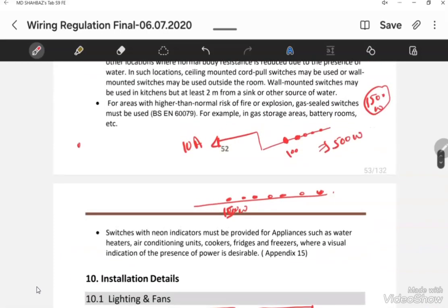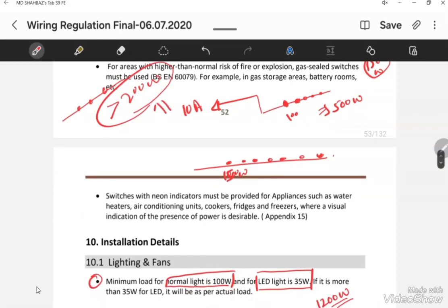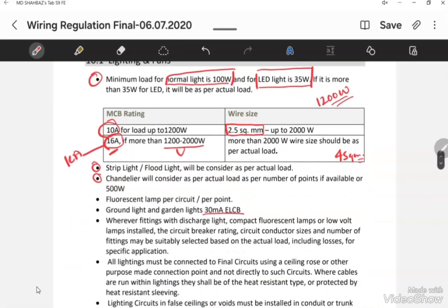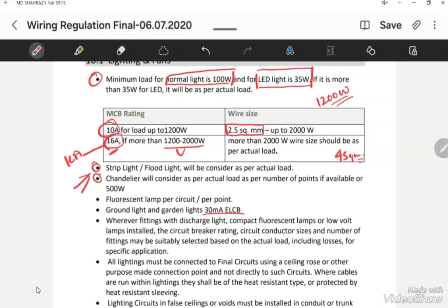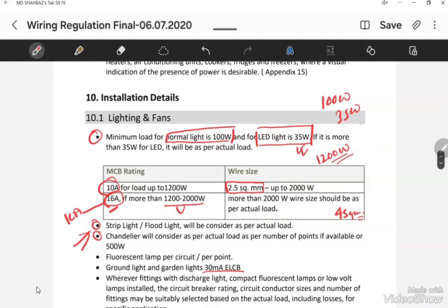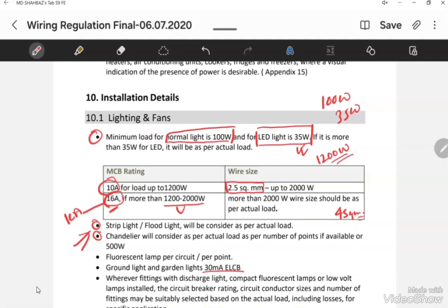If the light load exceeds 2000 Watt, we must reduce the number of lights in that circuit to bring the total load within 2000 Watt, and provide a 16 Ampere breaker. For strip lights, use the actual rating mentioned on the strip light. For chandelier lights, one chandelier is considered to be 500 Watt load.